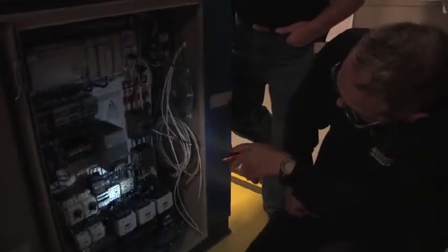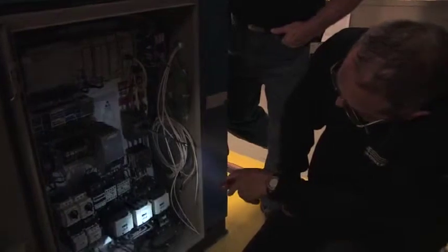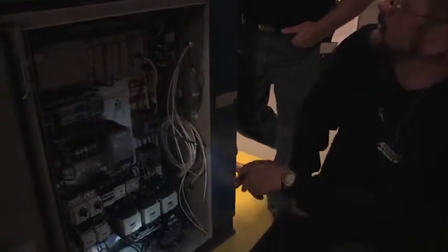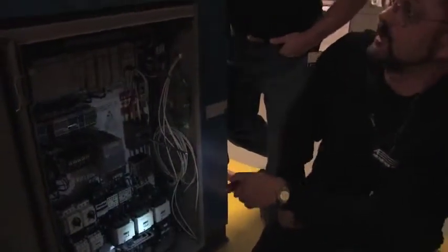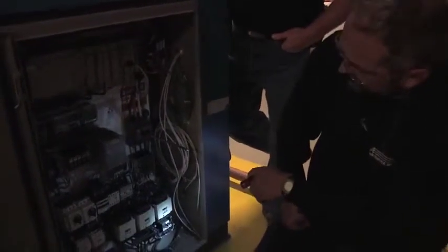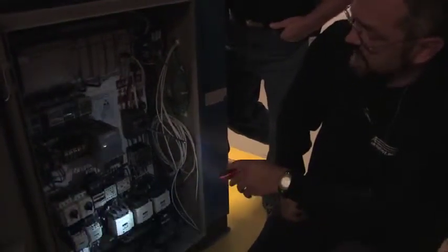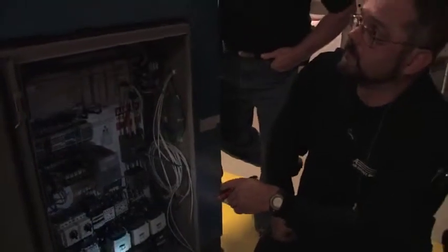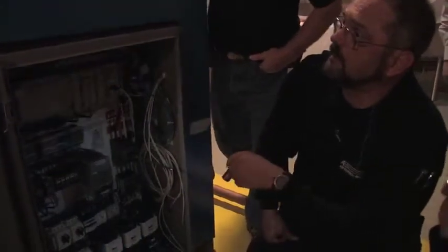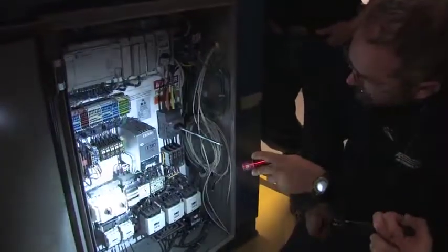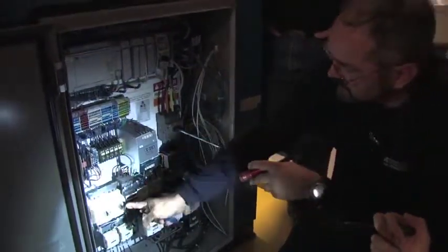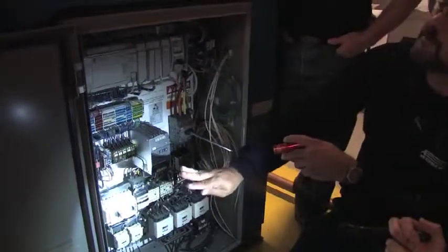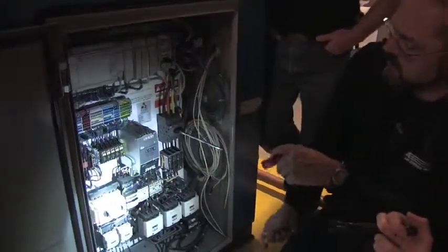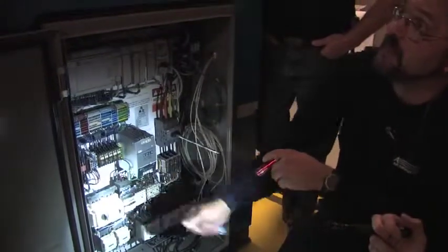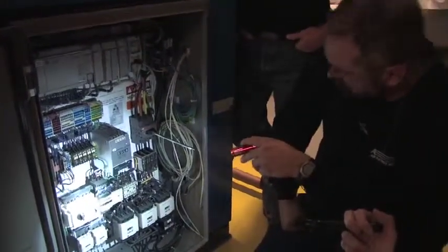Distribution block for the main power. And our main contactor set, these are, again, not variable speed drives, but they're Y delta, so it's a soft start. Biggest thing to remember about this is if you have a motor overload trip, if it's the fan motor or the oil pump motor, it's going to be one of these. If it's tripped, this handle will be at 45 degrees. Okay. And in order to clear it, you have to turn it all the way off and then turn it back on. Almost like a breaker where you have to go to full off.